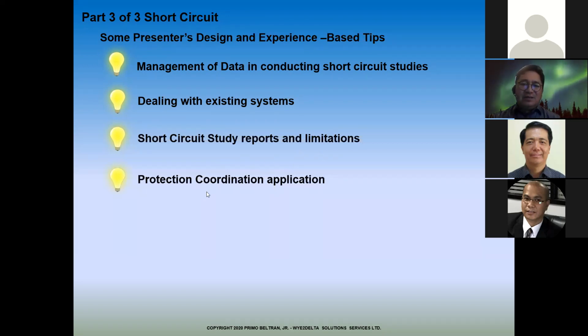Protection coordination application - when we calculate the buses, our withstand rating is based on total contributions. But for protection coordination, it should be the actual calculated current that will flow to the device for a specific fault point. If you have a fault downstream of a breaker, you don't use the total bus current - you use the current that flows through that device, what the CT will see. So our branch current flow calculations from part 1 are very useful here.